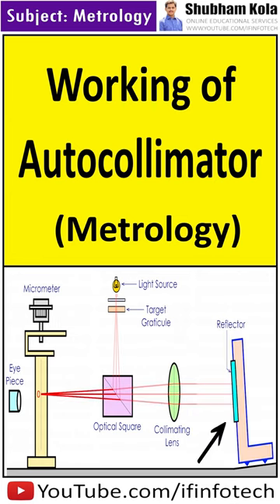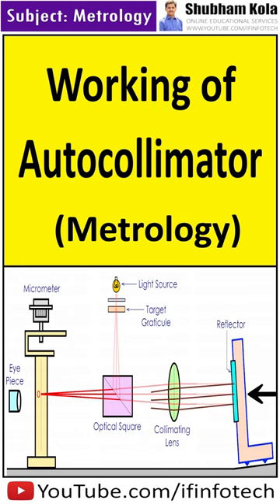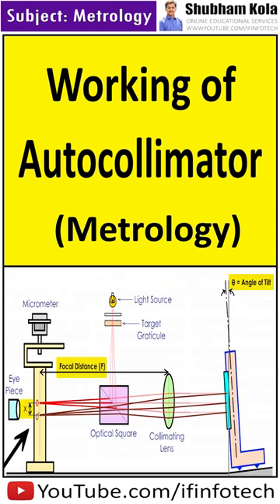And if the reflector is tilted to a small angle, then the reflected light will be displaced by twice the angle of tilt and will be brought into focus to point O', which is displaced by distance x. The distance x can be measured with the micrometer.